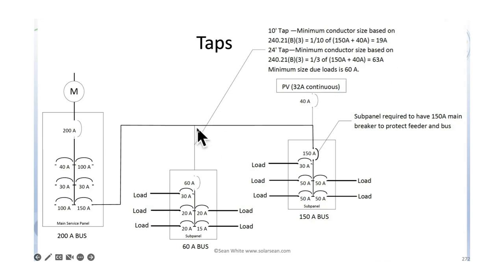And if we were going here using the 25-foot tap rule, this conductor would have to be at least 63 amps, but the overcurrent protection device would only have to be 60 amps. So this conductor, before we added solar, would only have to be 60 amps. But now this conductor with solar would have had to have been 63 amps. So you can see how you're getting kind of close there in that situation.